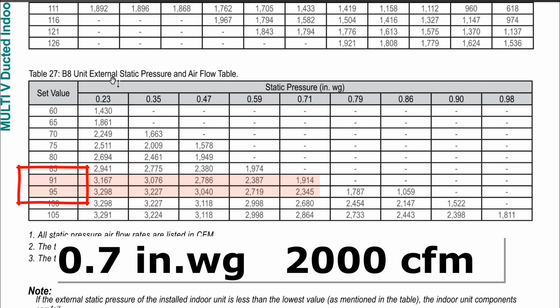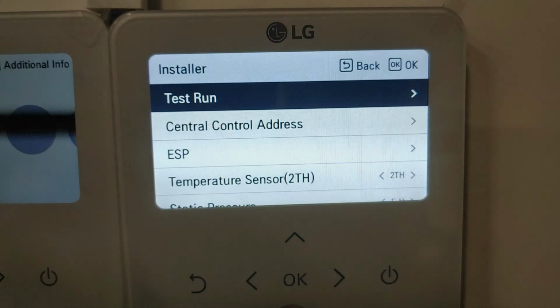Let's go back to our example. As we discussed, we need to set up set value 92. Go to ESP. Here you have selection of 5 speeds: high power, high, medium, low and slow. So for ducted unit we need to set up low, medium and high. Let's say we'll go to high, and we have range from 1 to 255. Okay, if we need to set up, you can just hold and go to setup 92. Press OK. Change has been completed. We just set ESP settings for high speed of fan value.